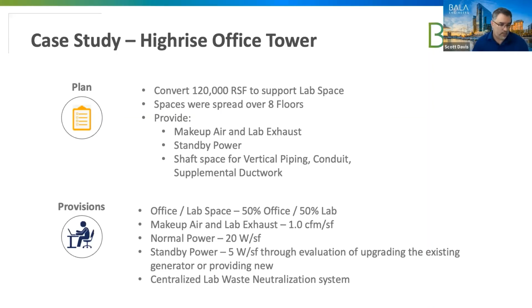Initially, looking at these first 2 floors coming out of the gate, they were originally looking to consume about 40,000 CFM of the total available air. Since we're at 80,000, that meant 2 floors out of 8 would take up 50% of the allotment. We brought that to their attention, and worked with a lab planner to focus on exactly how many fume hoods we needed and other requirements, which allowed us to reduce that airflow back down.